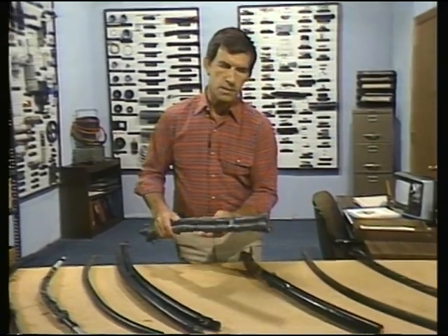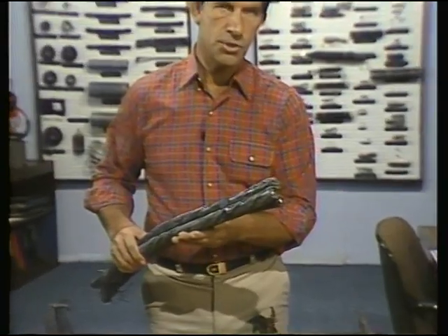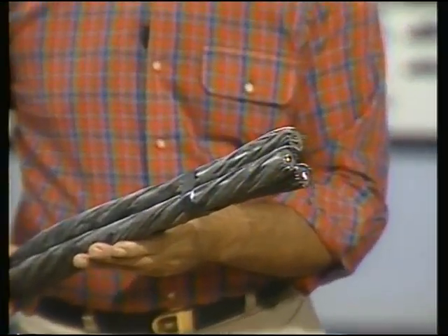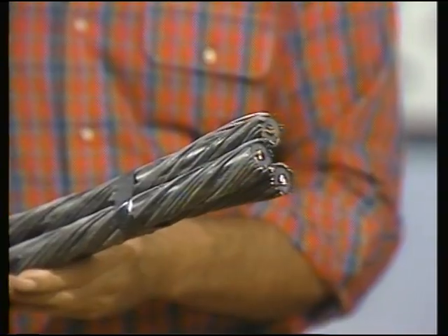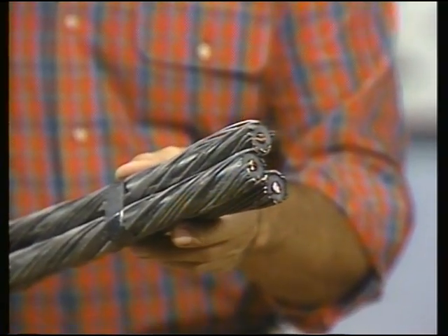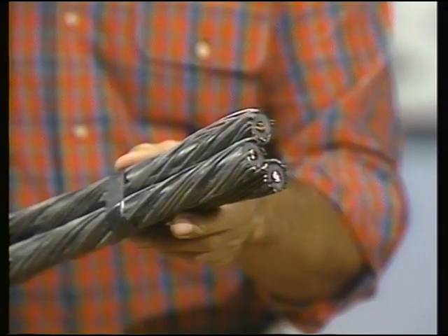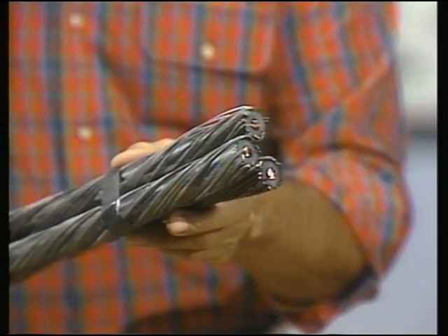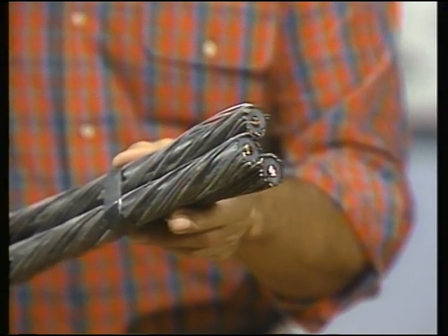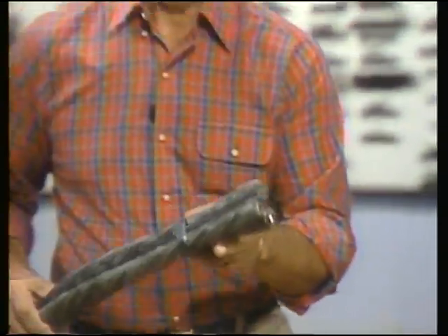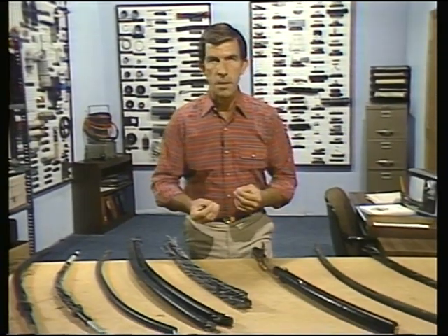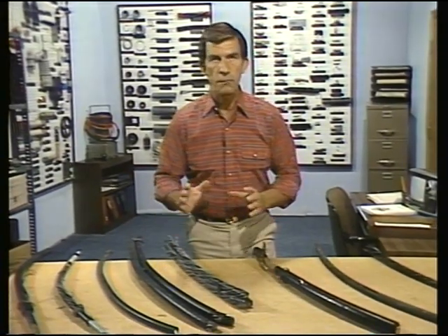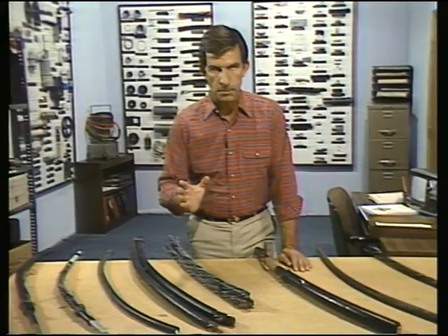Now, the need for this relief is the reason for the cable's metallic shield layer. The metallic shield layer, or on this cable, the concentric wire shielding, serves as a drain for static charge buildup. This concentric wiring may also have other functions in the system, which you'll learn more about later in your training. Now, the metallic shield is grounded. The shield is in direct contact with the semiconductive layer beneath it. The static charge is dissipated through the shield to ground, preventing any serious static buildup.